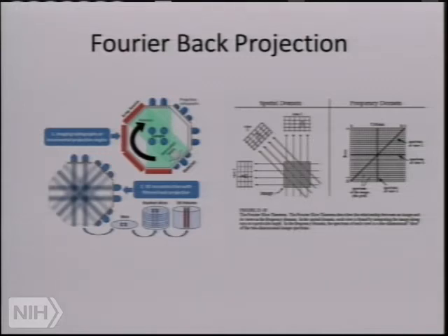And then if you back project all of those projections into virtual space, you can see that you could reconstruct those 4 different tubes. And that's the theory of back projection reconstruction. Each one of those can form a slice. You can stack those slices and do some image processing that will enable them to become a 3D volume, so you can look at the image in any plane that you choose.